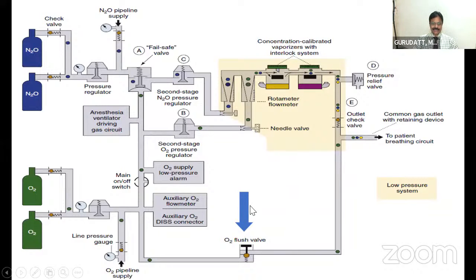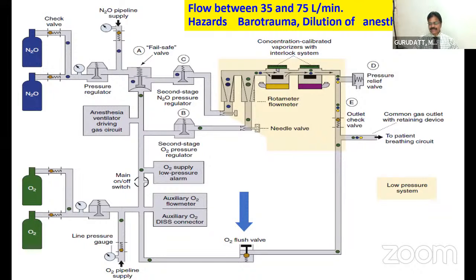Another thing you can see in this figure is that the flush valve oxygen will directly flow to the common gas outlet. So it is going to bypass the flow meter assembly, and also the vaporizers. Because of this, high pressure gases are provided to the patient. It can produce dilution of gases, because it is bypassing the vaporizers and the flow meter. So there can be lighter planes of anesthesia if you accidentally open the flush valve, or it can also produce barotrauma. So that is the problem.